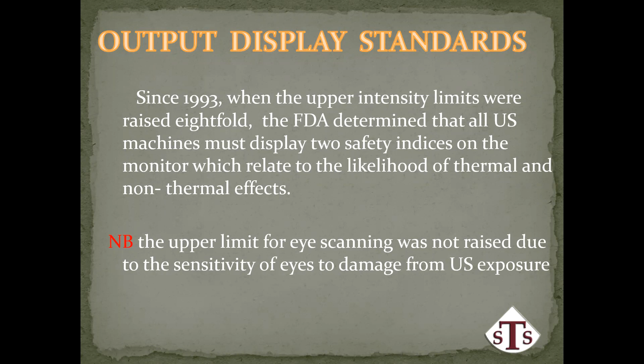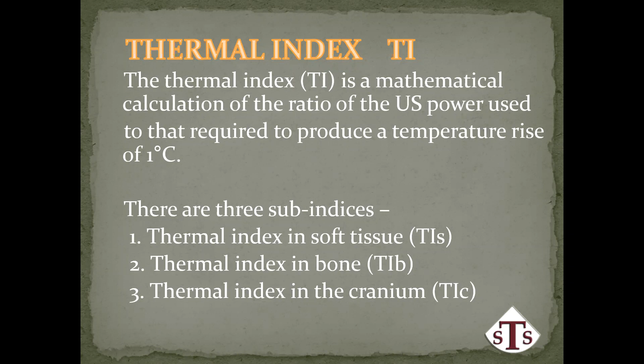So the thermal index, TI, is a mathematical calculation, and it's the amount of ultrasound power used to this mathematical requirement that will give a temperature rise of 1 degree. And this is where some of the other researchers have an issue, because this is a mathematical solution and not a real life solution. So this is a little bit controversial. They have 3 sub-indices: this index in soft tissue, in bone, and a special one for the cranium, because as with radiation, the central nervous system, particularly the spine and the brain of the fetus, is most sensitive to damage. Now, bone absorbs ultrasound energy more than any other tissue, and in doing so, it will heat up. So tissues next to bone, i.e. the cranium with the brain inside, may heat up more than other tissues.